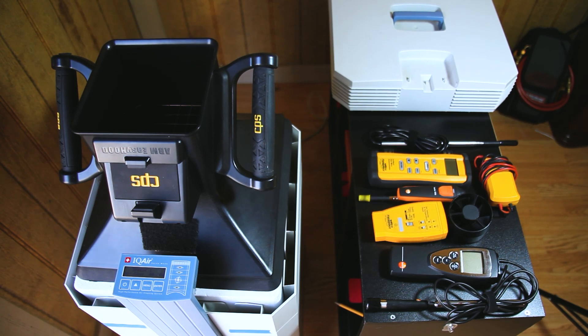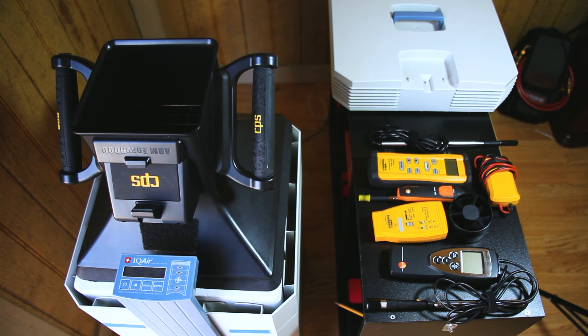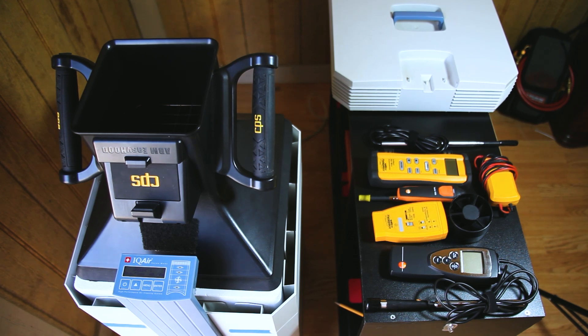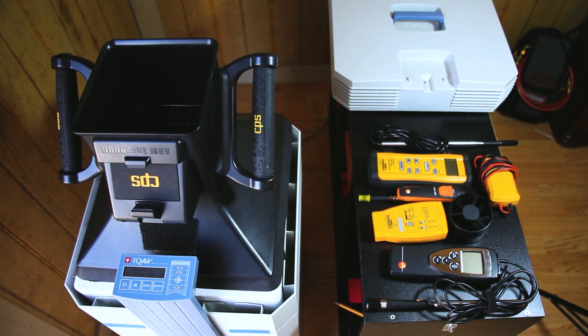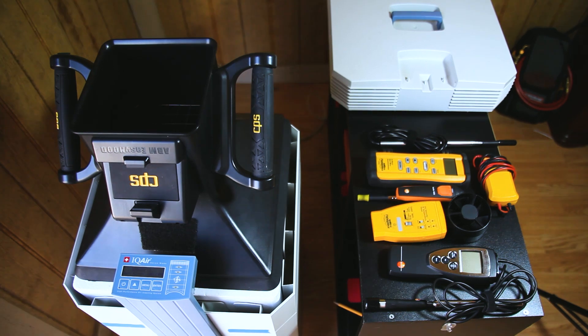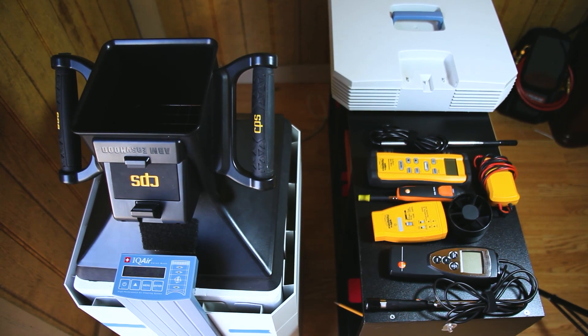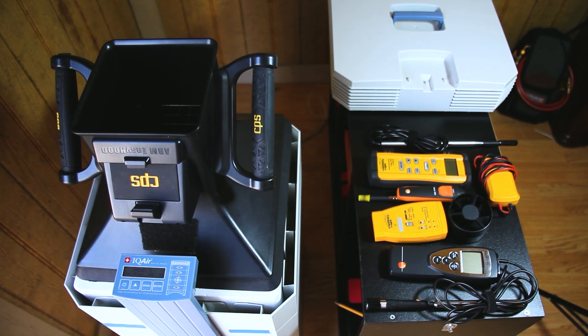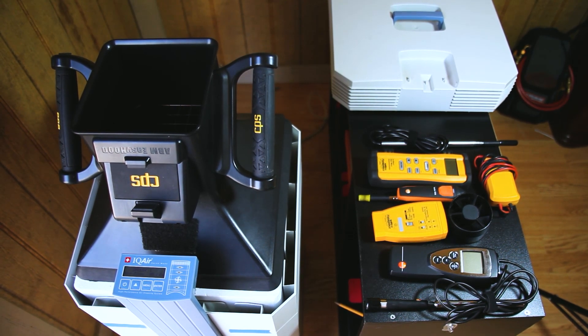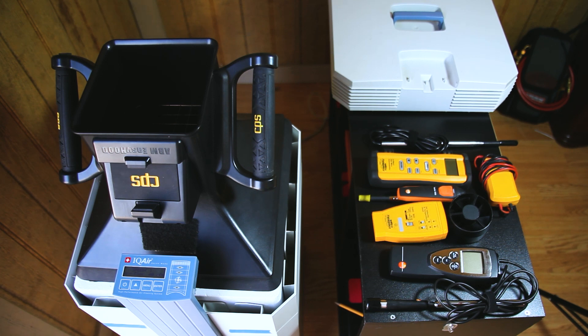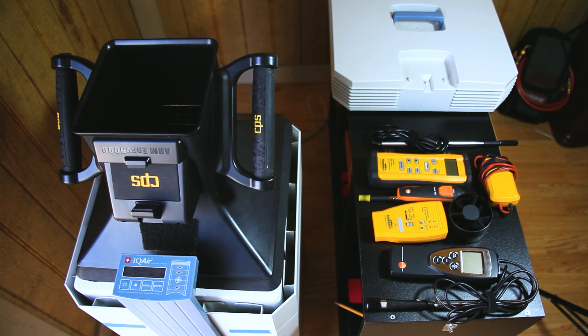Although it was a little bit high on the lower velocity, lower airflows, it was pretty accurate toward the middle range and the higher range. So pretty good. Not to mention, it's a pretty old unit, so it's definitely within the tolerances for its age. All in all, a pretty good buy.